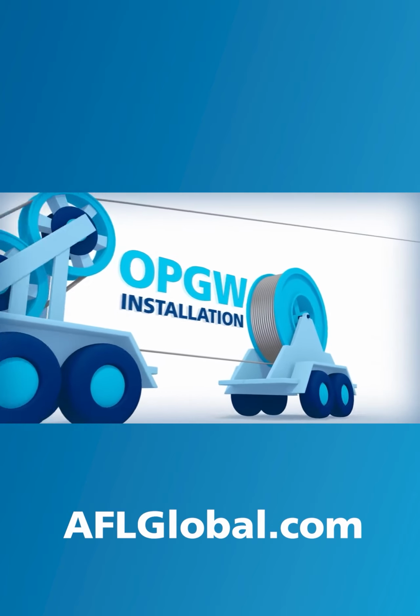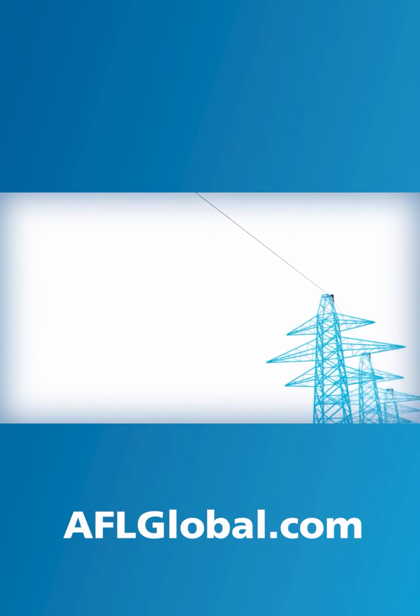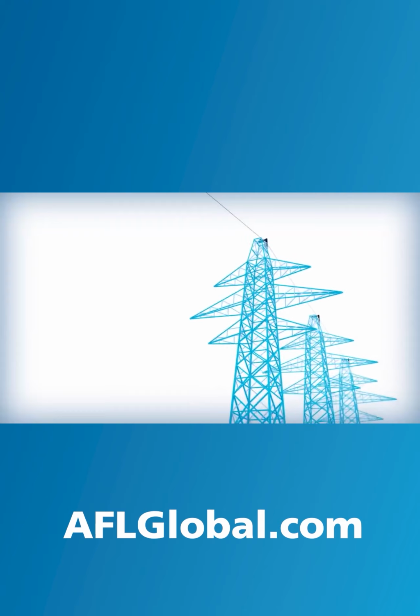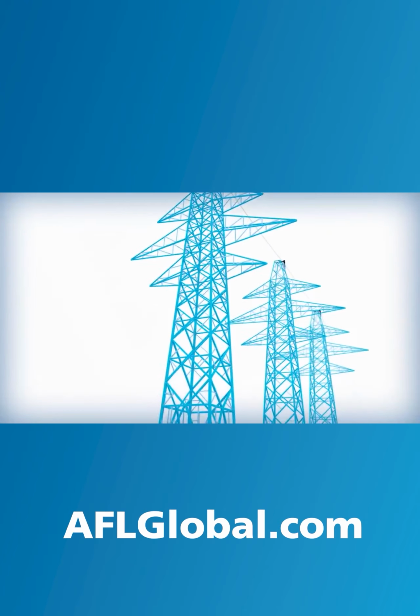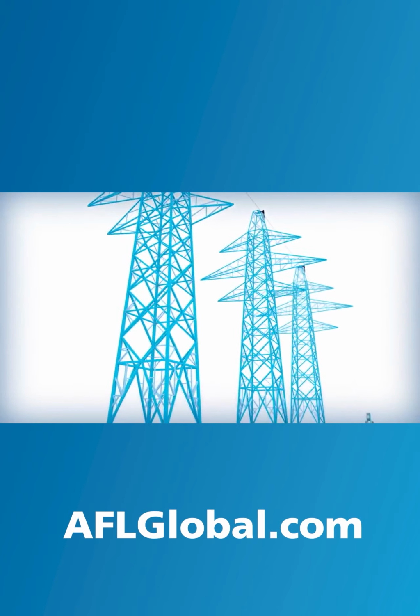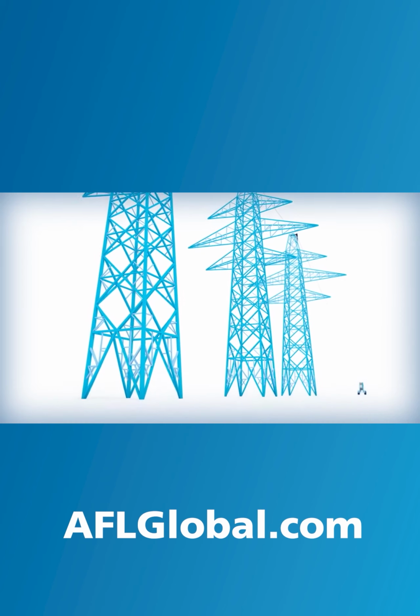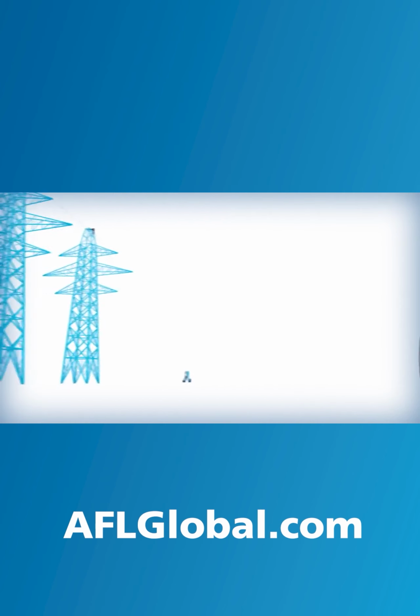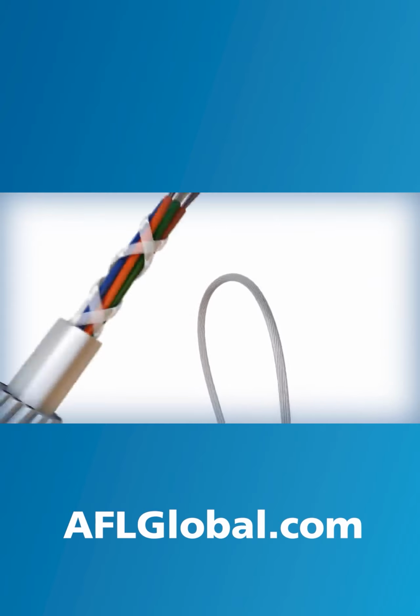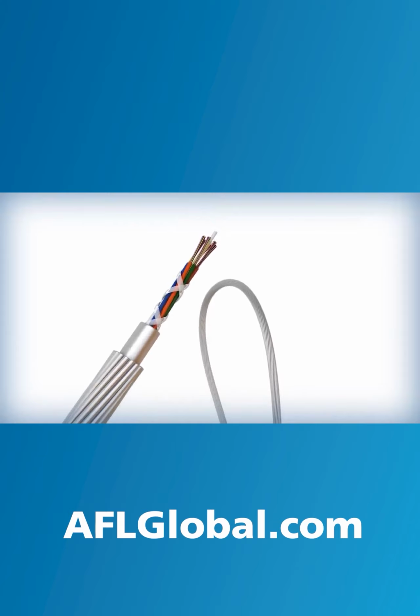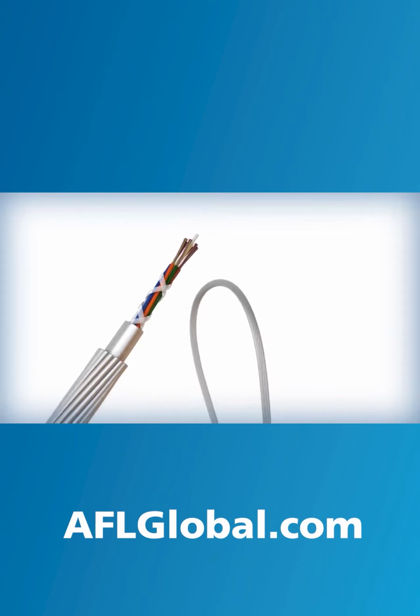OPGW was developed as a communication pathway on transmission lines. It also offers protection against faults and lightning. OPGW can be installed using typical conductor and shield wire stringing methods with minor variations. During installations, care should be given to avoid tight bends and excessive tensions that could crush the OPGW's fiber-bearing units.